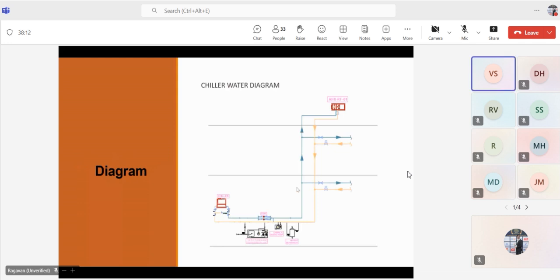Here you can see this diagram. Usually, the chilled water system is a closed loop system. Let's take a look at the diagram. This is a detailed schematic of the chilled water closed loop system. The key components are involved in the loop. You can see there's a chiller, and you have the pump, and you have this air separator, and then you have the pressurization unit, and the longest path of the pipe is there, and pipe fittings and valves and everything is there.